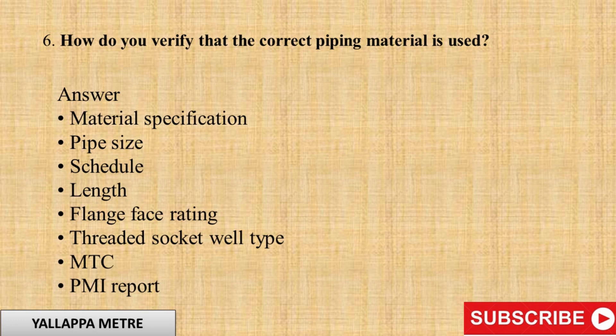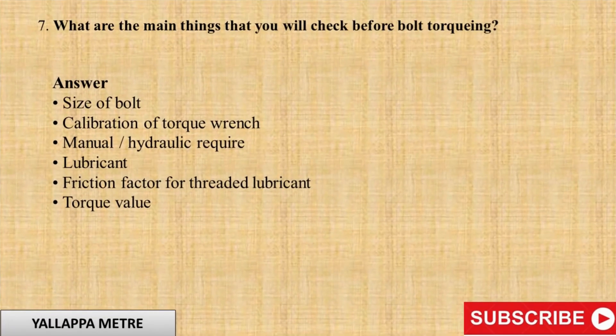Question 6: How do you verify that the correct piping material is used? Answer: Check material specification, pipe size, schedule, length, flange face rating, threaded or socket weld type, MTC (material test certificate), and PMI report.